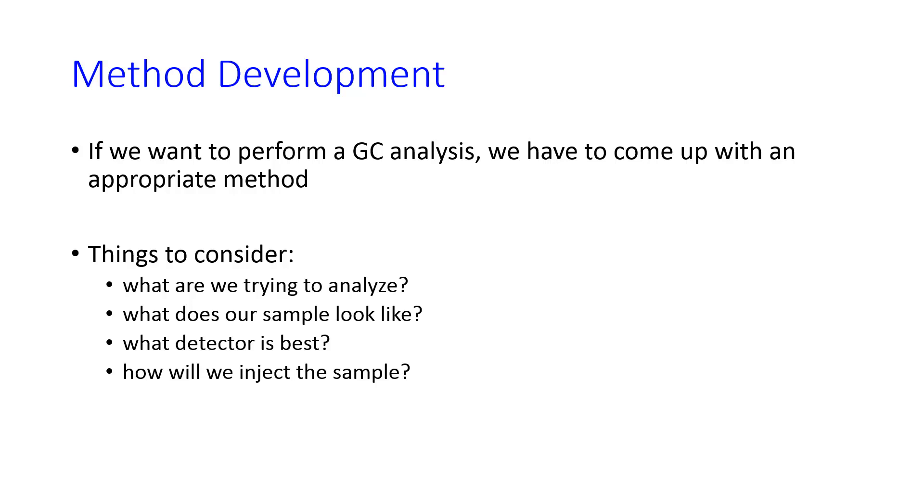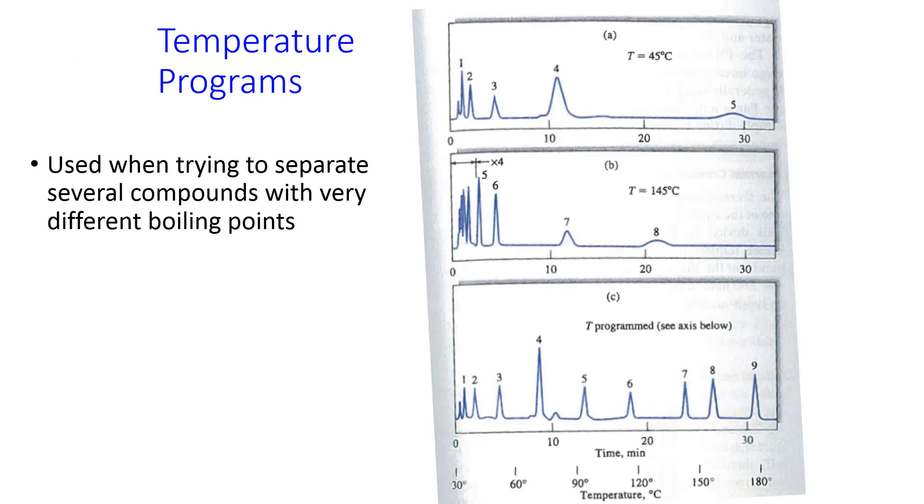The reason to consider especially the identity of the analyte is that if the analytes that we're trying to separate have very similar boiling points, it may be very difficult to separate them. Or if we have very different boiling points, the separation may take a long time. The way to get around this is by using a temperature program, where the temperature starts out low in order to get a little bit of initial separation of things that have very similar boiling points, and then ramps up quickly to a high temperature to drive things off the column that have a high boiling point.